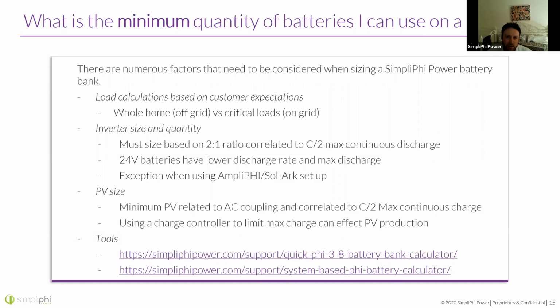PV size is also something to think about when it comes to minimum quantity of batteries. So if you're AC coupling, you need to consider that your battery also needs to be double the PV array size, or your array needs to be half of the battery bank size. So if you have 10 kilowatt hours of battery, you do not want more than 5 kilowatts of PV.